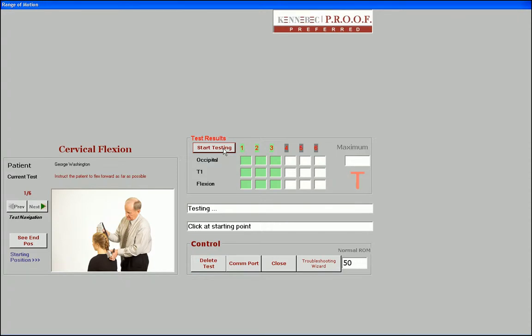At this point, the patient would be asked to go to the starting position with the device applied as seen on the screen. This allows us to lock in the starting position. Once you get feedback from the system telling you that the data was received, you are able to ask your patient to perform the range of motion. Once the patient has moved with the device applied, you may lock in the ending position by clicking on the device.